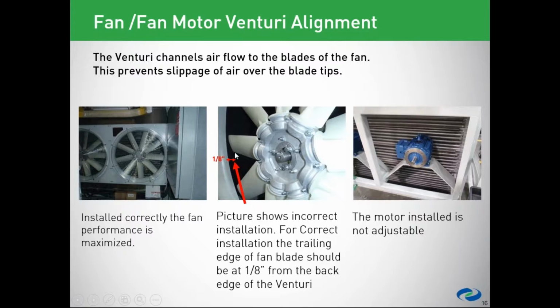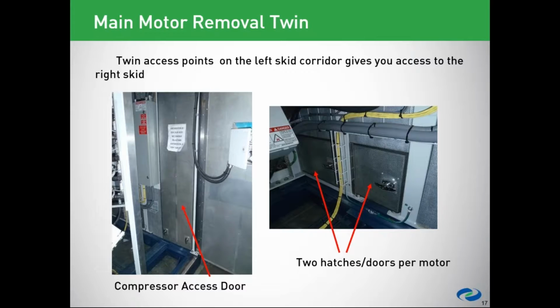Now, in the center picture, we see the hub is pushed onto this quite a ways, and I did that on purpose to show you that the fan blades are in the wrong position in this picture and need to be moved so that the trailing edge, follow my pointer, is 1/8 of an inch in from the trailing edge. So where I'm pointing is roughly 1/8 of an inch in from the back edge of the Venturi itself, and that makes sure that all of that fan is being used and that the air is not slipping off over the blade tips. And getting this into position and bolted down takes maybe about 20 minutes maximum.